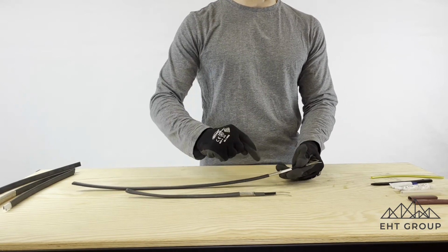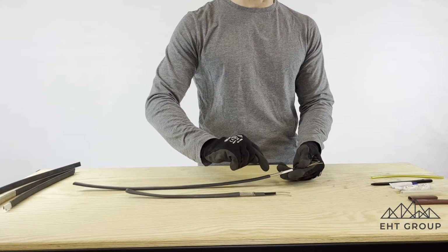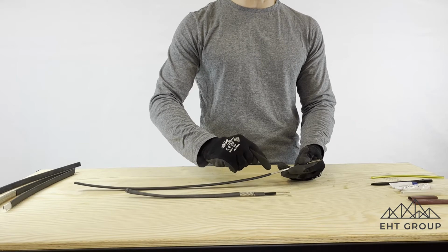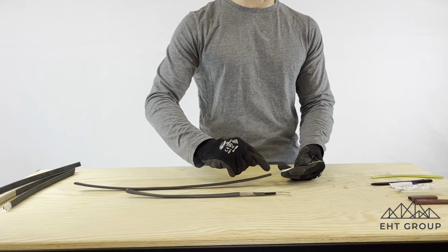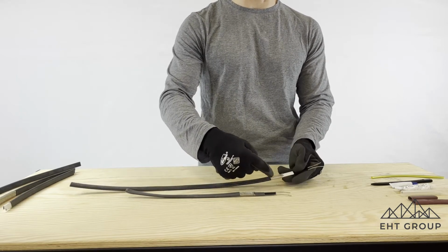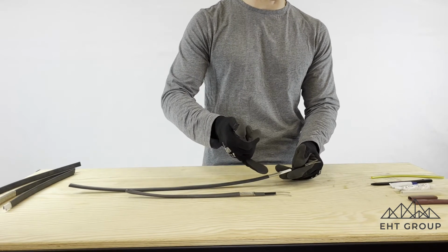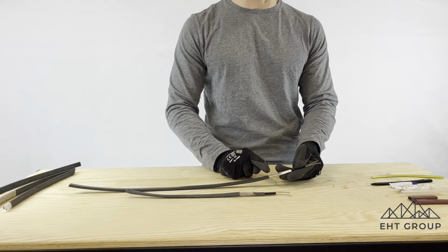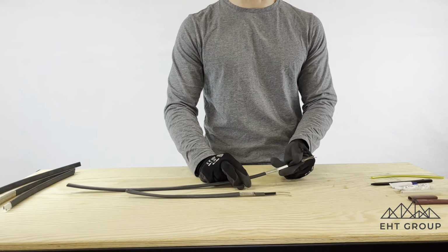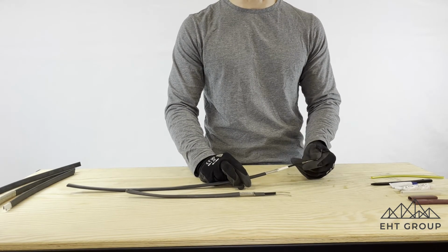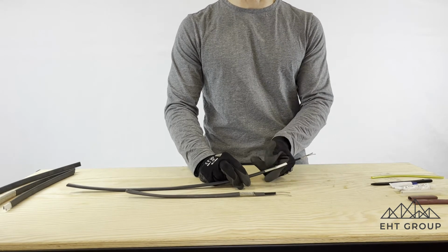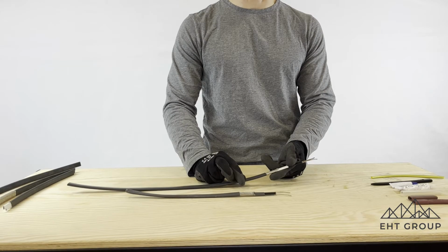And what we typically see is that during a termination point, when the outer sheath is cut, there needs to be some very, very special care taken in terms of how you cut this sheath. And what oftentimes happens is a knife will go through the sheath, and then your braid will be in very close contact to your semiconductive core or your bus bars. And we really want to make sure that we're taking good care when we're cutting the SR cable.